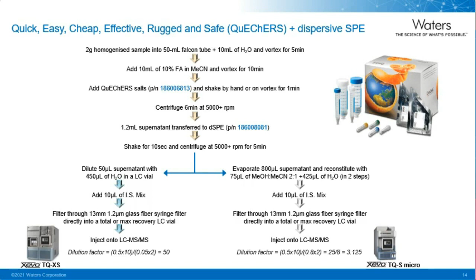1.2 milliliters of supernatant are transferred into the dispersive SPE tube, shaken and centrifuged. At this point, we have two options. We can either dilute the supernatant 1 in 10 with water and inject onto the Xevo TQ-XS with a dilution factor of 50, or we can evaporate 800 microliters of supernatant and reconstitute with 500 microliters of at least 85% aqueous and inject onto the TQ-S micro, resulting in a dilution factor of about 3.1.